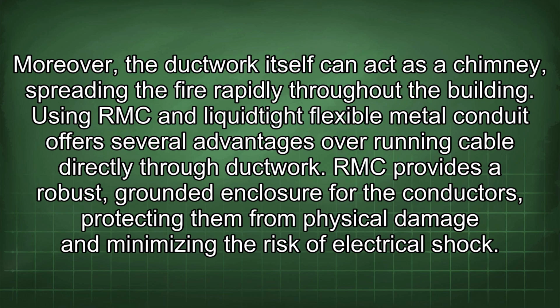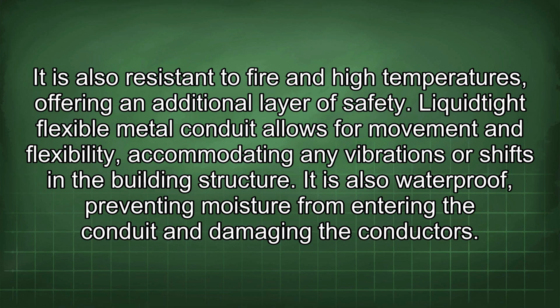Using RMC and Liquidtight flexible metal conduit offers several advantages over running cable directly through ductwork. RMC provides a robust, grounded enclosure for the conductors, protecting them from physical damage and minimizing the risk of electrical shock. It is also resistant to fire and high temperatures, offering an additional layer of safety. Liquidtight flexible metal conduit allows for movement and flexibility, accommodating any vibrations or shifts in the building structure. It is also waterproof, preventing moisture from entering the conduit and damaging the conductors.